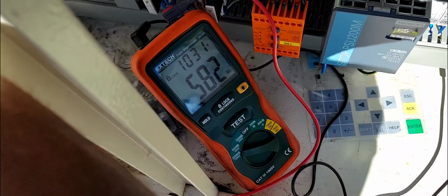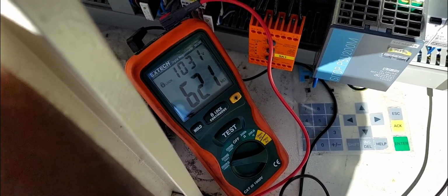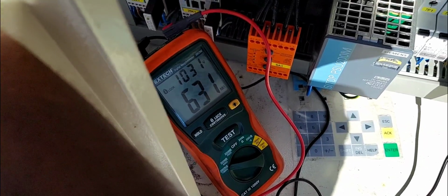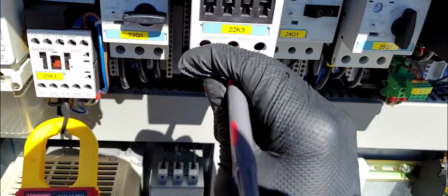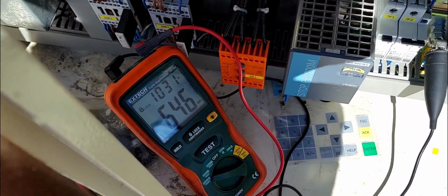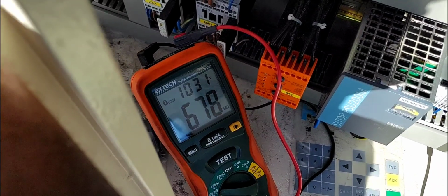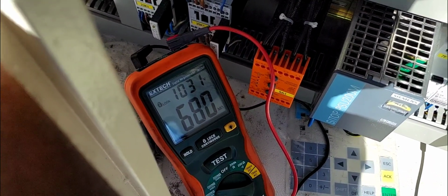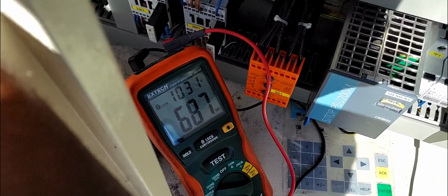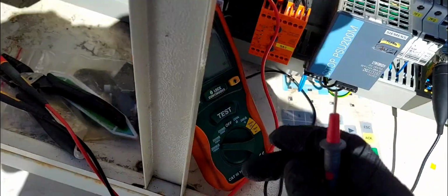We do another winding. Now, some of you pros might say, why am I checking from the contactor and not at the motor? That this is not a good test. Well, my answer is that this is a more effective test because I am killing 2 birds with 1 stone. I could sit here and go to the compressor, remove all the wires from the terminals and check only the compressor. However, that might test good.